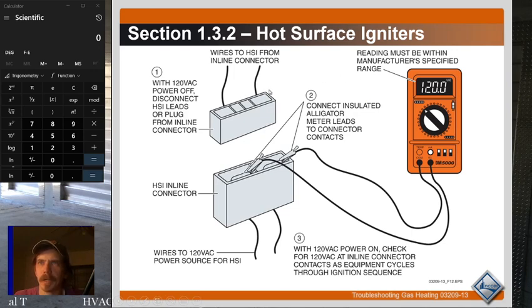Hot surface igniters. To test a hot surface igniter, you want to ohm out the hot surface igniter and check the resistance across it. Best thing really to do is look up what that specific manufacturer calls for resistance across it and see if it's right. Usually if a hot surface igniter is bad, it's open, right? It's got a crack in it. But you can diagnose a hot surface igniter that's starting to fail by seeing an abnormally high resistance, or an abnormally low resistance for that matter, but generally the resistance starts to go up, if I remember right, as they age. But you want to look up that particular hot surface igniter's normal resistance range, and if it's outside of that range, then you'll want to replace it. But if it's bad, usually it's cracked, so you'll have infinite resistance.